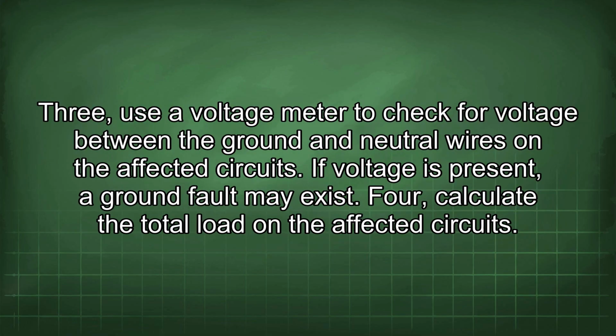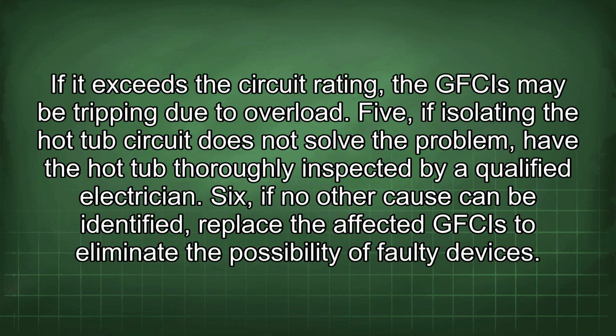3. Use a voltage meter to check for voltage between the ground and neutral wires on the affected circuits. If voltage is present, a ground fault may exist. 4. Calculate the total load on the affected circuits. If it exceeds the circuit rating, the GFCIs may be tripping due to overload.